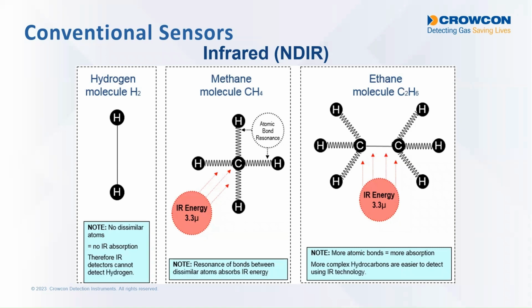And if these gas molecules are exposed to infrared energy at around 3.3 microns, then those atomic bonds resonate within the molecule, and that resonance absorbs the infrared energy and basically reduces the amount of infrared energy that's seen at the sensor. And it's that reduction of energy that the detector relies on to detect the gas. I've also shown a hydrogen molecule, which is H2. Because you don't have dissimilar atoms, there is no resonance within the molecule, and therefore you can't detect hydrogen using infrared technology.